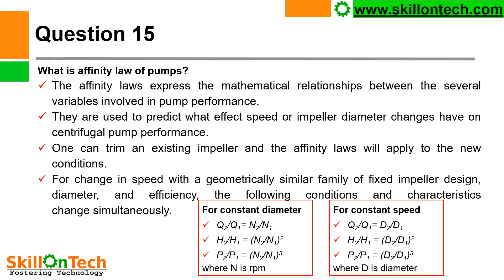What is the affinity law of pumps? Affinity laws express the mathematical relationship between the several variables involved in pump performance. These affinity laws are used to design prototype pumps. They are used to predict what effect speed or impeller diameter changes have on centrifugal pump performance. One can trim an existing impeller and the affinity laws will apply to the new conditions.